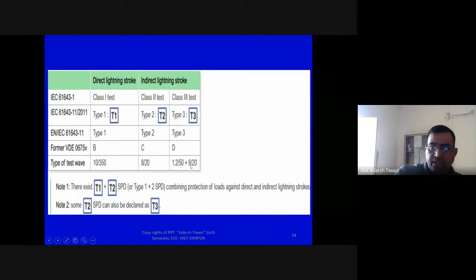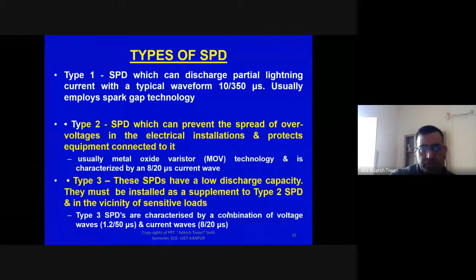So type 1 basically is a typical 10 by 350 microsecond protection, which is usually by the spark gap technology. However, the type 2 technology is metal oxide varistor, which will give protection from 8 by 20 microsecond current. And type 3, which is a combination of voltage 1.2/50 microsecond and current of 8 by 20. It is a combination protection. So this is used inside the building. So we will discuss which type of protection is used where in terms of lightning zones.